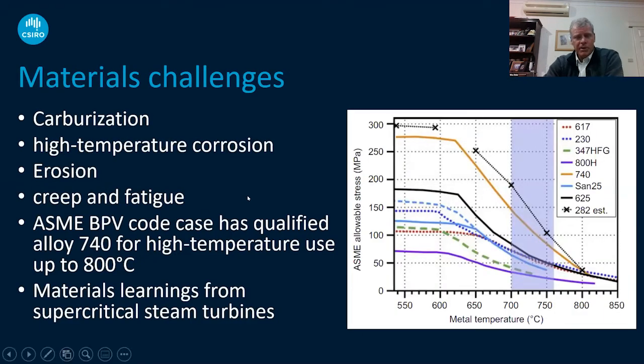There are significant material challenges: carburization, where carbon from the CO2 reacts with elements inside the steel to form carbides along the grain boundaries, leading to embrittlement; high temperature corrosion; erosion due to the very high speeds from the high density CO2; and creep and fatigue. You just can't go and choose any old steel from the ASME code.